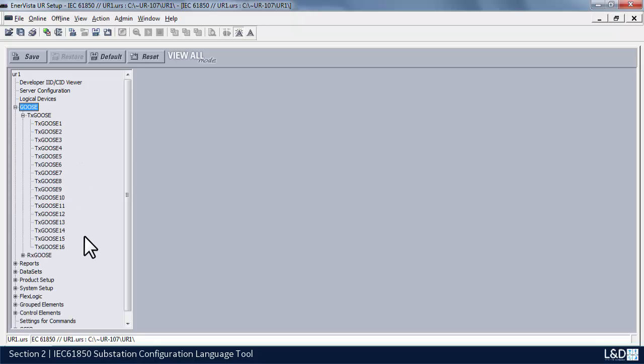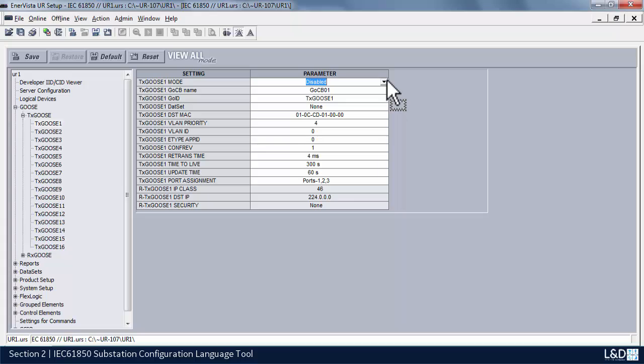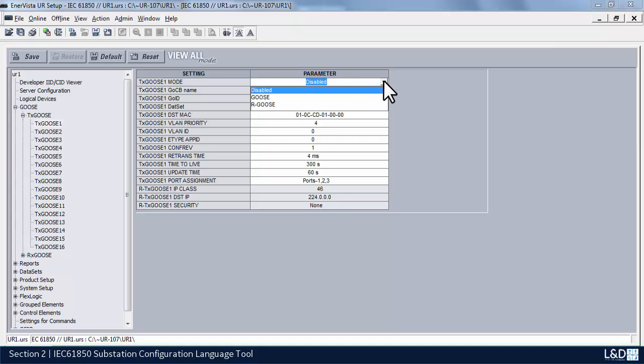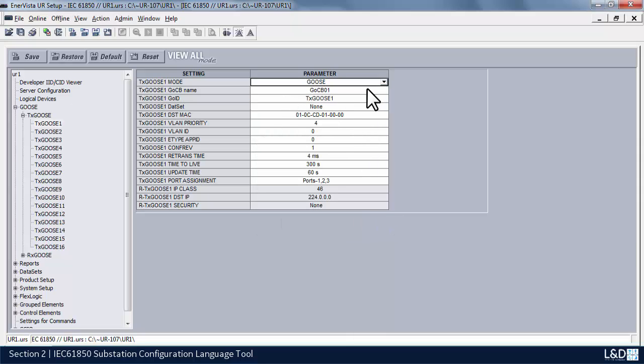When we expand on this, there are 16 GOOSE messages that we can publish. Let's open this up and go through the menu structure quickly. The mode — basically disabled — means it's turned off. We have a couple of different modes: the standard GOOSE and the routable GOOSE. If we select the GOOSE, it gives us this information.